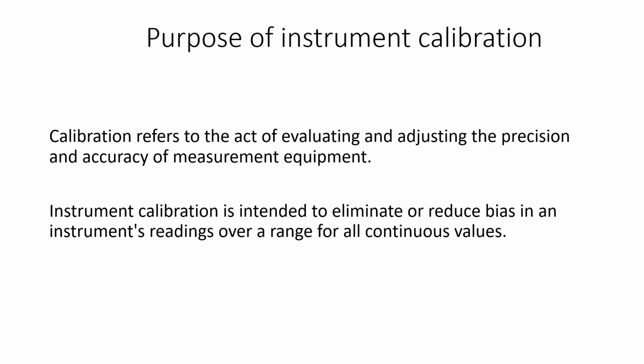Okay, so that means the main purpose of calibration is the act of evaluating and adjusting the precision and accuracy. Precision and accuracy both are important. Precision means that it works in the same way in every reading. That means it is giving readings which are close to each other, not creating a lot of variation, and those readings are also close to the accurate reading, right? So we are adjusting the precision and accuracy of the measurement equipment.